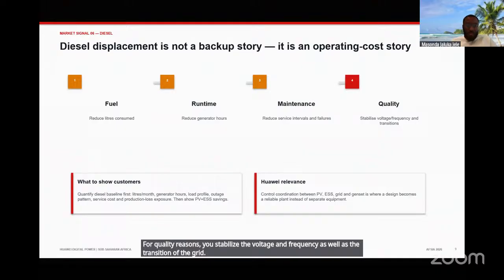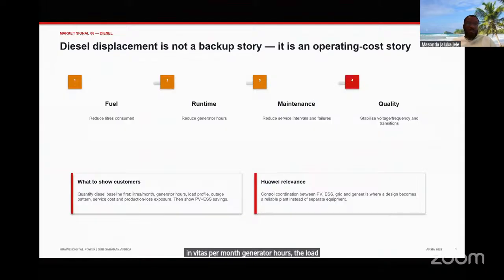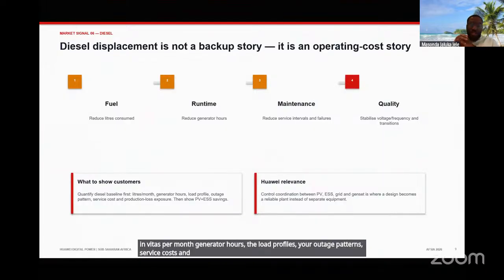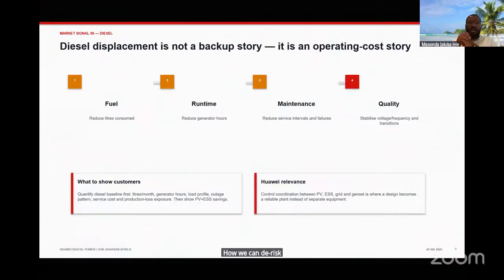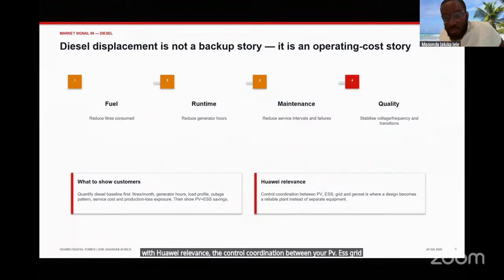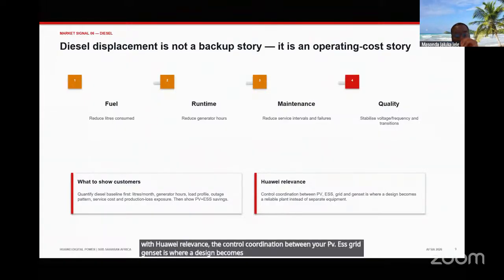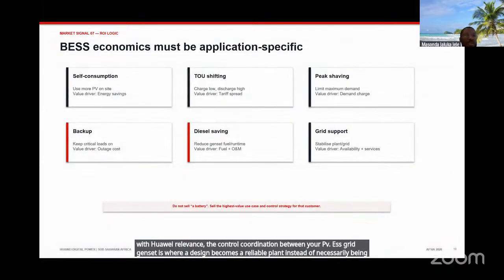What to show customers? Quantify the diesel baseline first: liters per month, generator hours, load profiles, outage patterns, service costs, and production losses being exposed. And then we show the PV and ESS savings for our customers, such that they can understand how we can de-risk the reliance on diesel gensets. With Huawei's relevance, the control coordination between your PV, ESS, grid, and genset is where a design becomes a reliable plant instead of separate equipment.